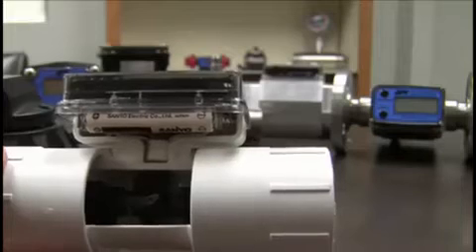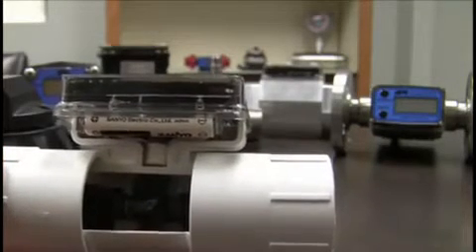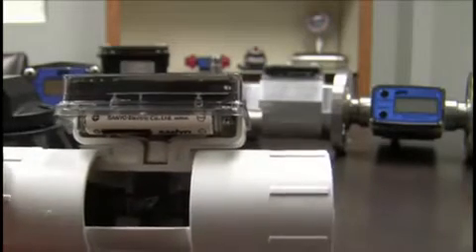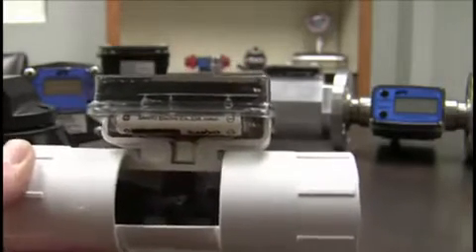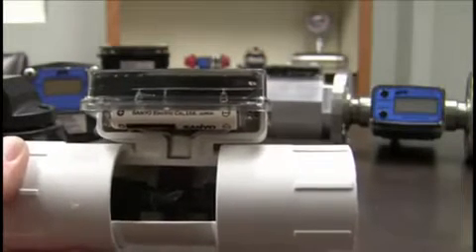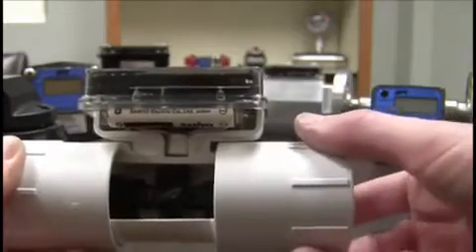The problem with the turbine meter is, you put water through it, that turbine spins like crazy and works just great. But then all of a sudden you put oil through it, something that's a lot thicker, and that oil is going to make the turbine spin a lot slower, even though you're putting the same amount of fluid through it. So how do you work with something like that? Well, that's where a positive displacement meter comes into play.